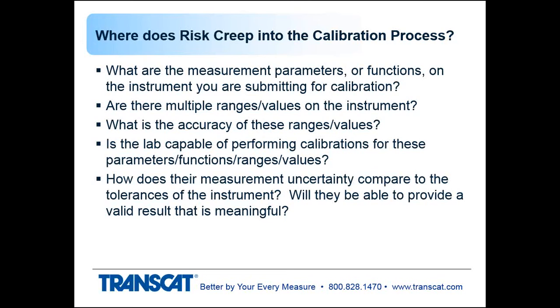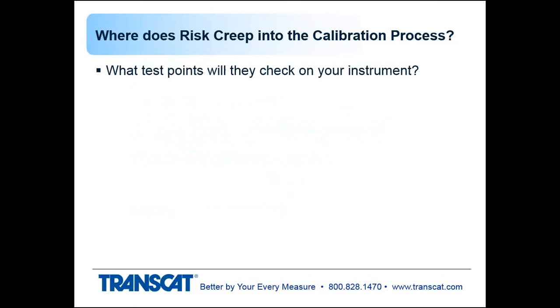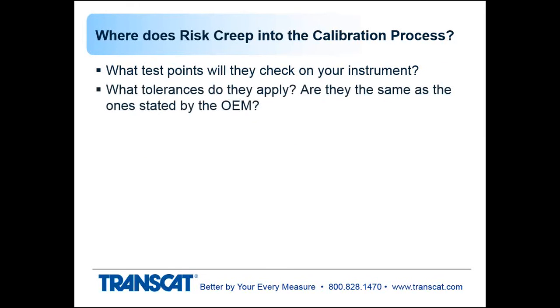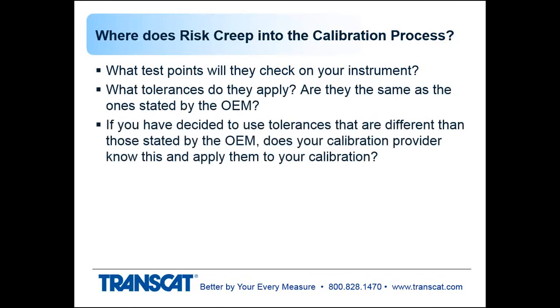So looking at those ratios, if they're very close to one another, or what we would call a 1-to-1 ratio, then that's going to increase the amount of risk for false acceptance of that calibration measurement value, which then could impact the readings on the instruments or product where the instrument is used. What test points will the calibration lab check on the instrument compared to what you're expecting they should be checking based on supporting the application where the instrument is used? What tolerances did they apply? Are they the same as the ones stated by the OEM or stated by you if it's a custom cal? If you decided to use tolerances that are different than those stated by the OEM, in other words, a custom cal, does your cal provider know this, and have they applied that to your calibration?